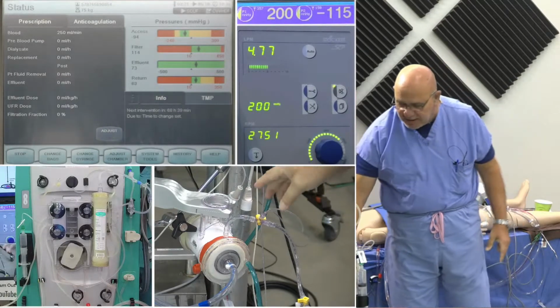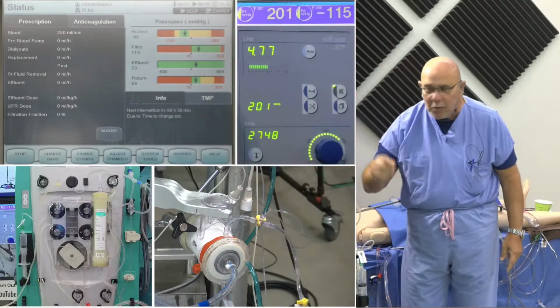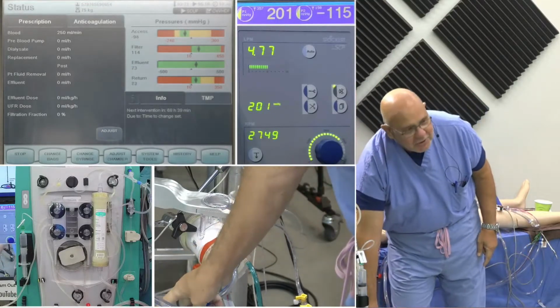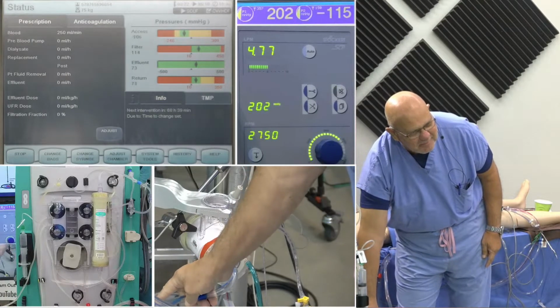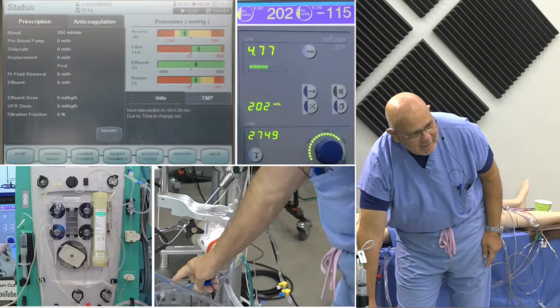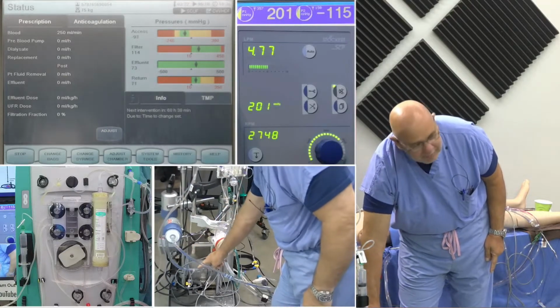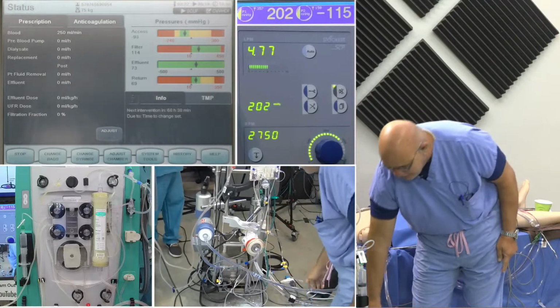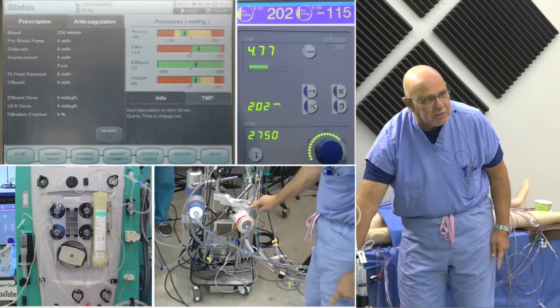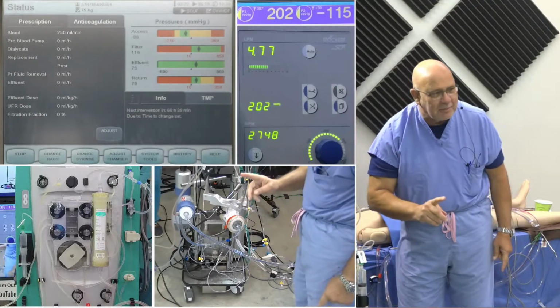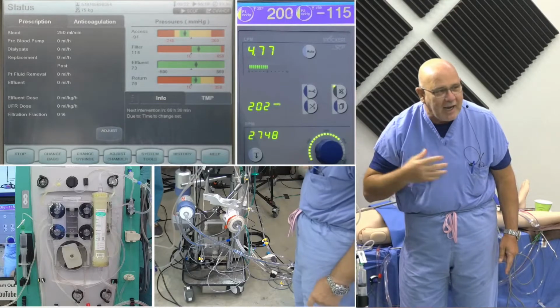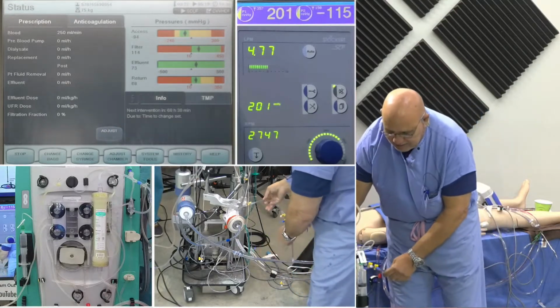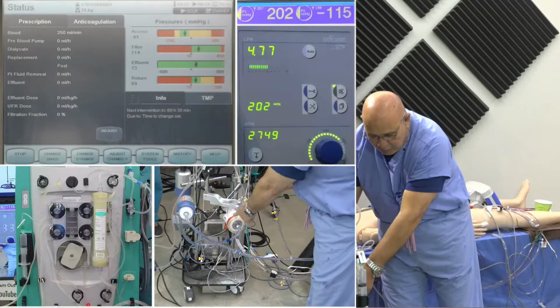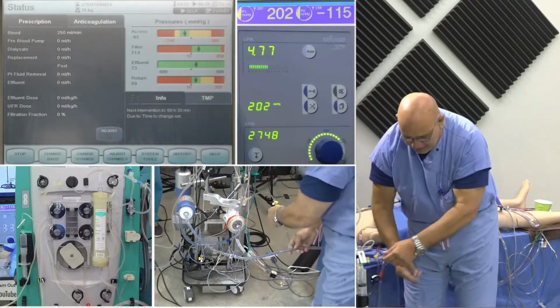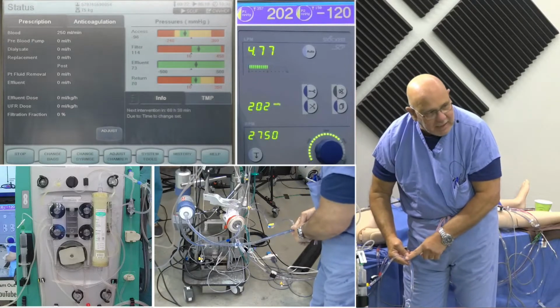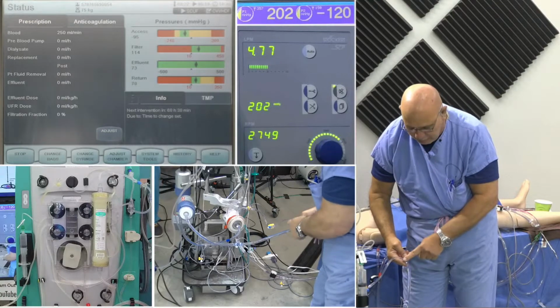So very interesting. It's reading 200, which is somewhere between what our pressure was here, and you can go ahead and zoom out, what our pressure was in the line going from the centrifugal pump, the highest pressure area, and the return. So it's between those two. Now I'm going to do something very interesting, and why I do it this way. So what I want you to notice is I have a line that is a shunt line going from the top of the oxygenator back to the access side of the ECMO, the ECMO access line.